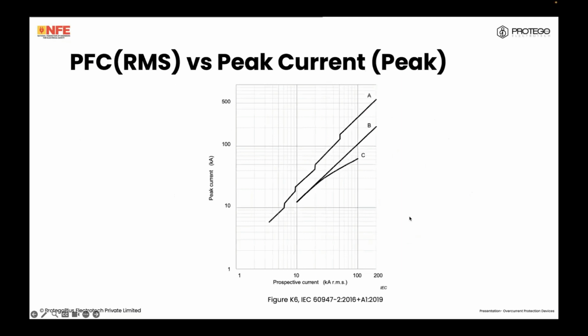There's also the prospective fault current, which is given in root mean square, and your peak current, which is given in peak. We all know that if we say 230 volts RMS, the actual waveform, if we look at it on an oscilloscope, goes much higher. Basically, when it comes to circuit breakers tripping, you generally have to consider the peak current value, and for long exposure, it is the prospective fault current in RMS. So if you want to do selectivity analysis, to see if an upstream breaker will trip, you have to look at the peak current value.